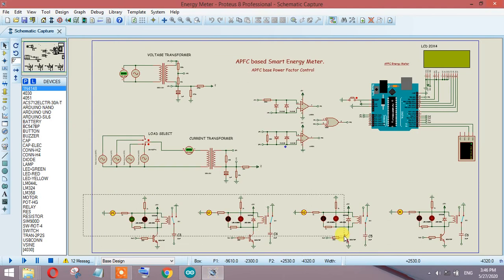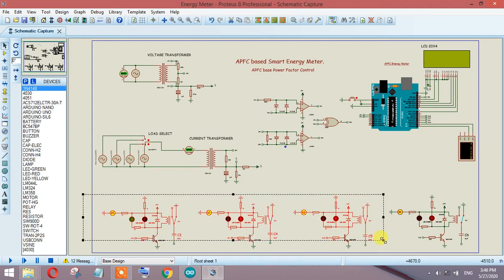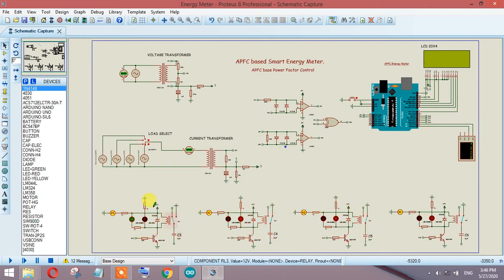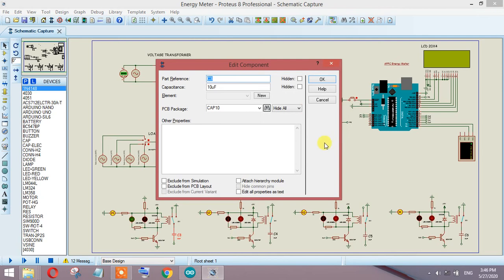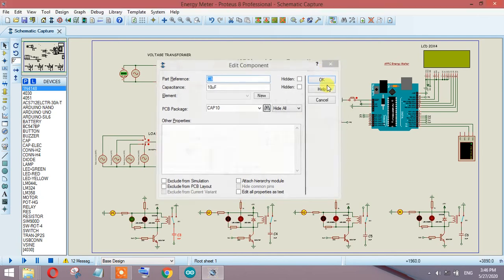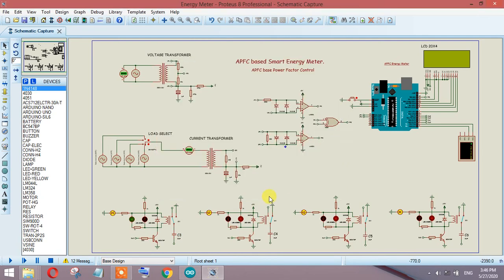You can see there are basically four relays, and each relay is connected to one capacitor. The purpose is to demonstrate how capacitors will be added to make the power factor unity. For example, if the power factor drops to 0.5, a couple of capacitors will be added to make sure the power factor again becomes unity.